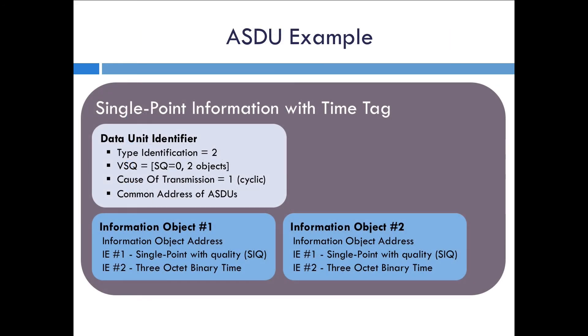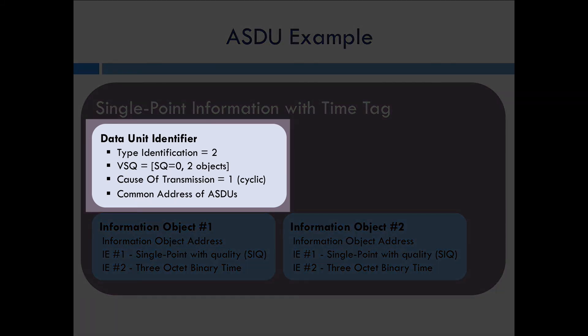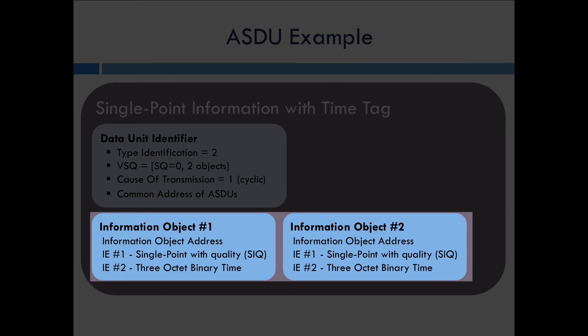As an example, let's put together an ASDU for single point information with a time tag. You include the single point with quality, a three-octet binary time, and the address for the object — that's the information object when those three things are put together. The data unit identifier will identify the type as type 2. The VSQ will indicate it's not a sequence ASDU. The cause of transmission — for a cyclic measurement from the outstation — would be set to 1. It also has the common address for the ASDU. In this example, there are two information objects, though you could have up to 127 in one single ASDU.